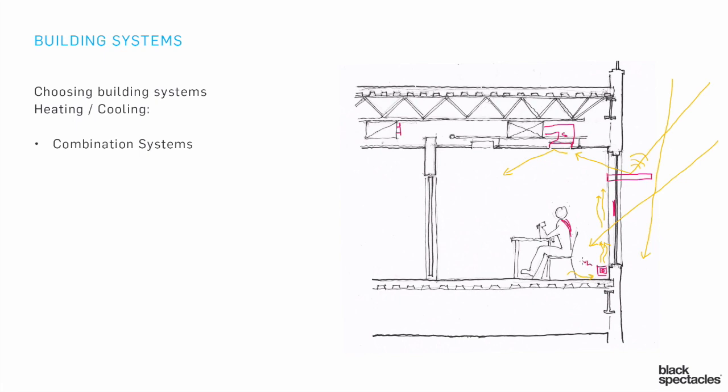So that baseboard heater is doing a lot of work — creating a convective element that deals with the window, and also delivering heat energy to the person. There's a radiant aspect too: the radiator is radiating to the body, which helps out-radiate the cold window situation. So even though the body is radiating heat toward the cold window, the radiator is radiating back to the body, creating a quite lovely warmth in that space.